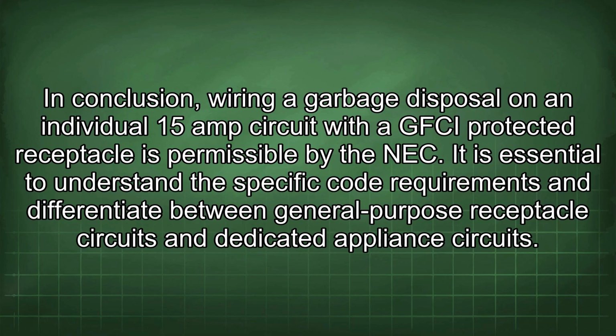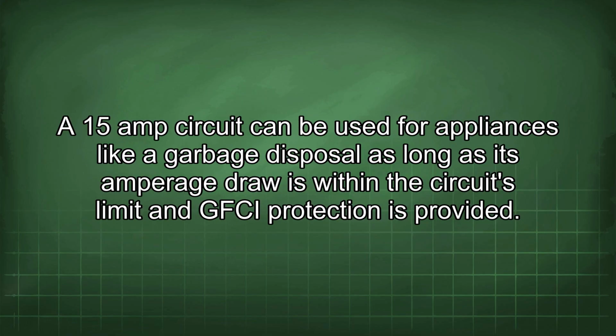In conclusion, wiring a garbage disposal on an individual 15-amp circuit with a GFCI protected receptacle is permissible by the NEC. It is essential to understand the specific code requirements and differentiate between general-purpose receptacle circuits and dedicated appliance circuits. A 15-amp circuit can be used for appliances like a garbage disposal as long as its amperage draw is within the circuit's limit and GFCI protection is provided.